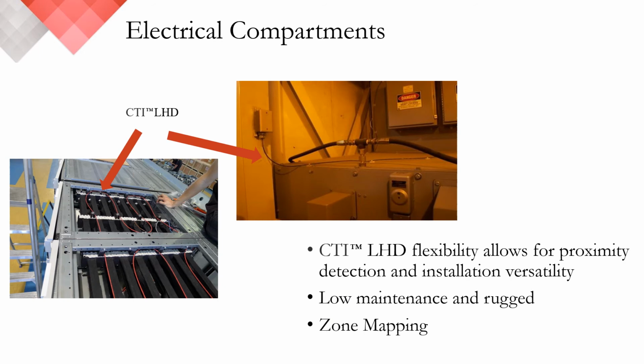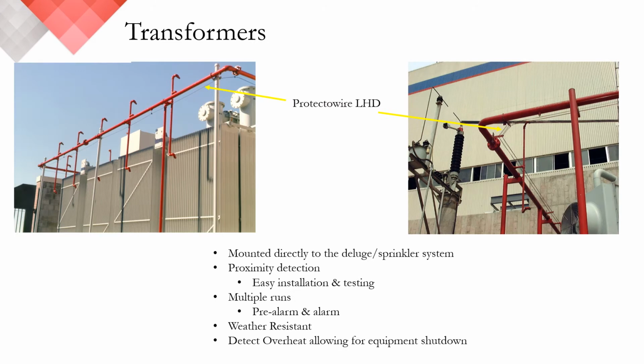And again, a great example of the versatility of linear heat in confined areas. Electrical compartments heat up very quickly. In transformer applications, we see linear heat being installed directly to the deluge system. In most cases, the linear heat detector will act as a pre-action or pre-alarm to initiate the alarm sequence. This is considered an integral aspect of the sprinkler's operation and should be located as close to the sprinkler heads as possible.